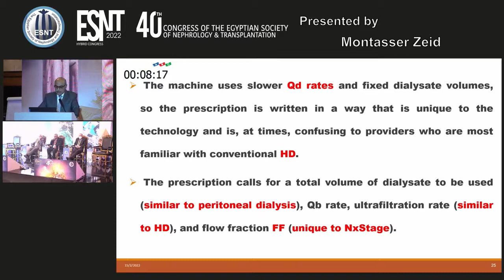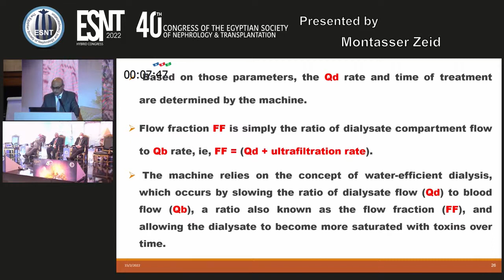the Qd rate and time of treatment are determined by the machine. Flow fraction is simply the ratio of dialysate flow to blood flow rate, and the machine relies on the concept of water-efficient dialysis, which occurs by slowing the ratio of dialysate flow to blood flow, a ratio known as flow fraction, and allowing dialysate to become more saturated with toxins over time.